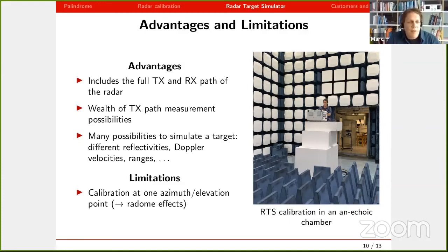We can also simulate a lot of different reflectivities and different Doppler speeds, so we can basically test the whole dynamic range and linearity of the system. There is one limitation. Because our system is set up at one point, we only calibrate the radar at one point. And if you want calibration at different locations, you need to move around our instrument.